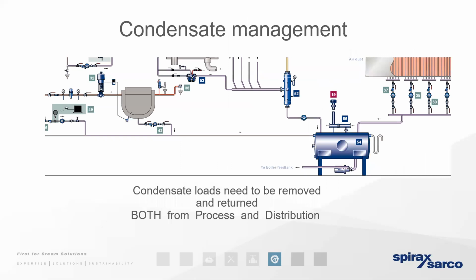So we've also spoken previously about the benefit of condensate. Condensate, it's hot water. But remember, we know that water's got a specific heat capacity of 4.19. And after all, condensate is water. So condensate exists whenever steam gives up its heat energy. That can be in the distribution pipework, and it can also be at the process. Now, condensate can cause a number of problems if it's left in the distribution steam pipework. Not only can we get that erosion, corrosion, and water hammer we've spoken about, but it can ultimately degrade the steam and reduce the energy value of the steam as it finds its way to the process. And if condensate's left at the process, it can back up and flood the steam space.